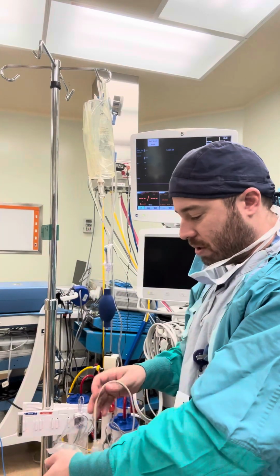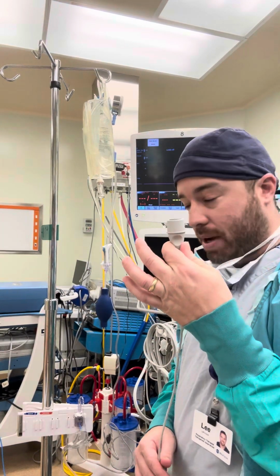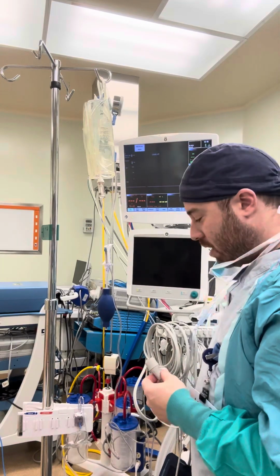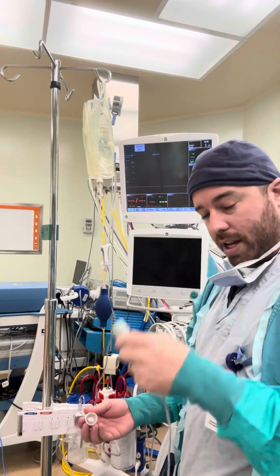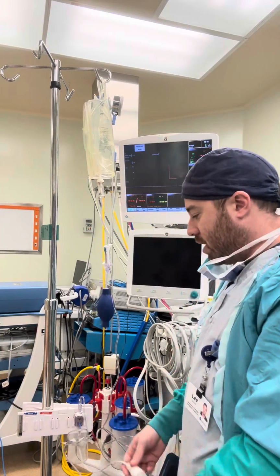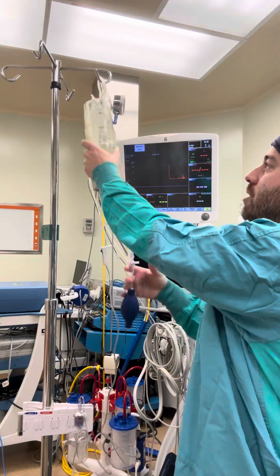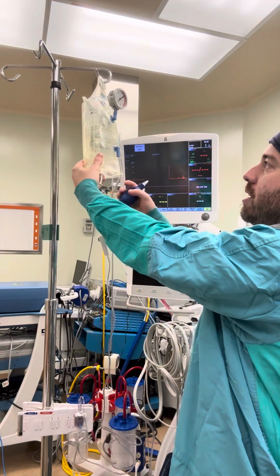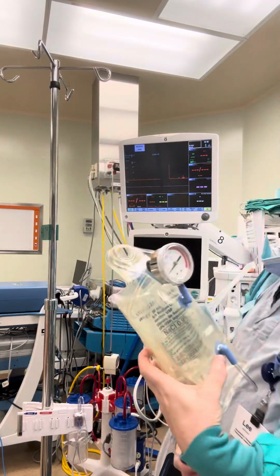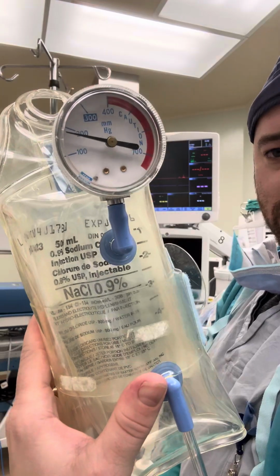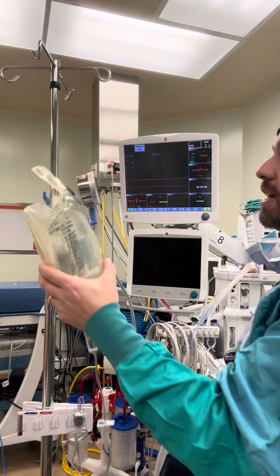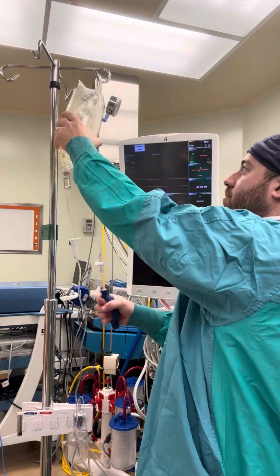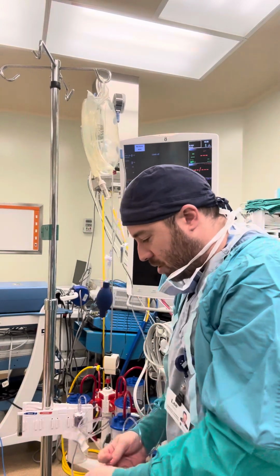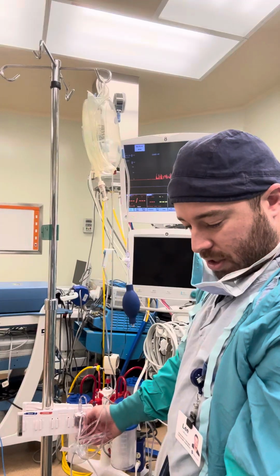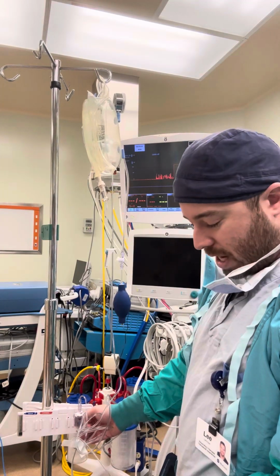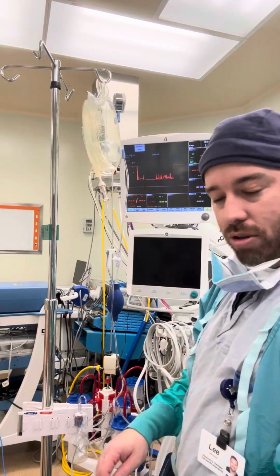The next thing I'm going to do is take my transducer from the monitoring system that we have here on our gas machine, and we're going to connect this. Once I've connected that, I'm going to prime this system to 300 millimeters of mercury. As you can see here, it's marked right onto the side. We're going to go slightly past that 300. What I also like to do, once that's pressurized, is give this system a really solid flush into a garbage can, and then double check to make sure that there are no bubbles in that system.